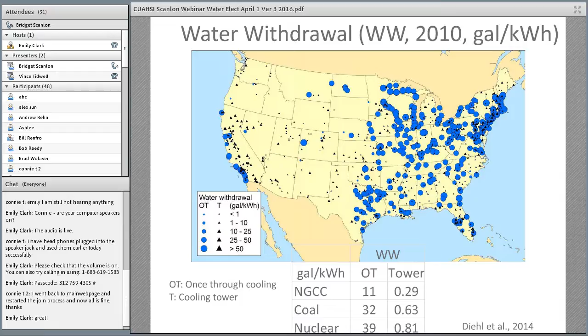Coal and nuclear plants have 30 to 40 gallons per kilowatt hour, whereas the natural gas combined cycle plants are about a third of that, because they include combined gas turbines with steam turbines, so it's about 11. The cooling towers have much lower water withdrawals, less than 1 gallon per kilowatt hour.